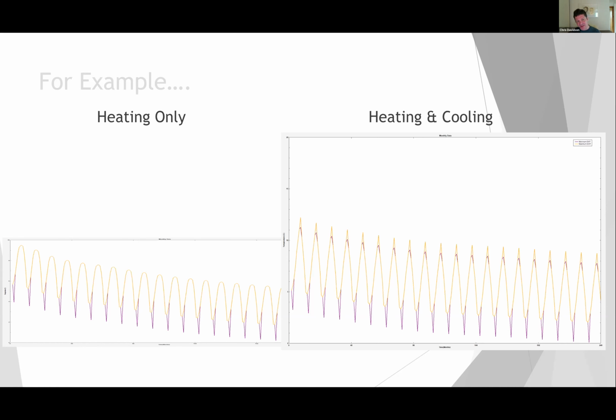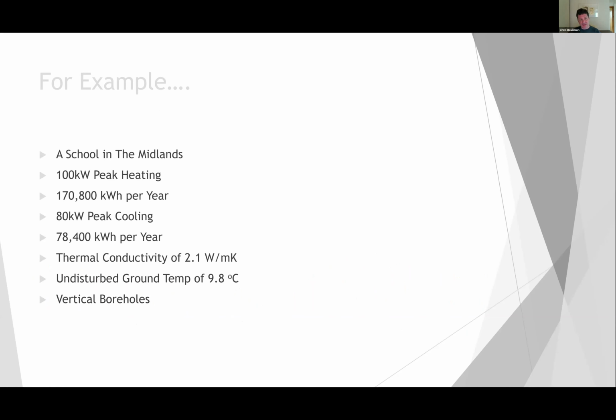If I look now at a second example, so same school in the Midlands, but we've got a much higher peak cooling load now and a correspondingly higher annual requirement for cooling. Everything else is the same. And if we run it, obviously, and omit the cooling, we get the same number as before, 2,508 metres of total borehole requirement to do that load. If we now look at adding the cooling into the system, then we take that down to 1,536 metres of borehole, which is obviously a dramatic saving.